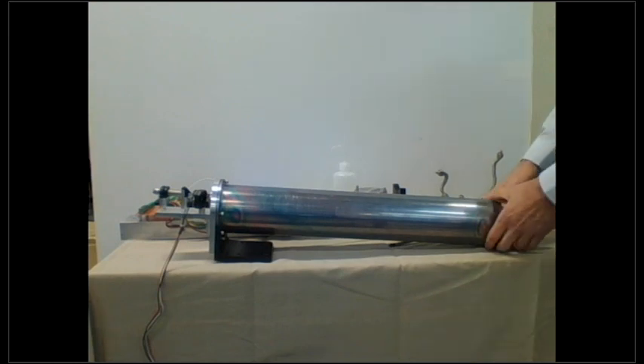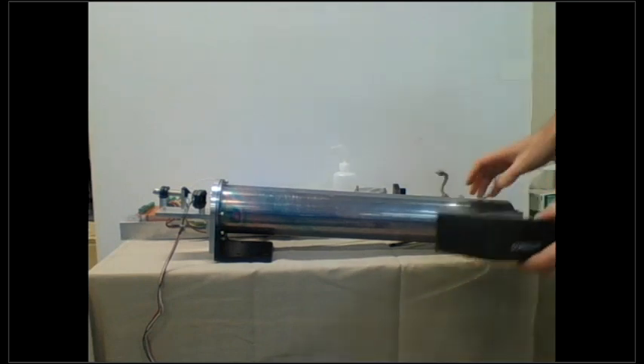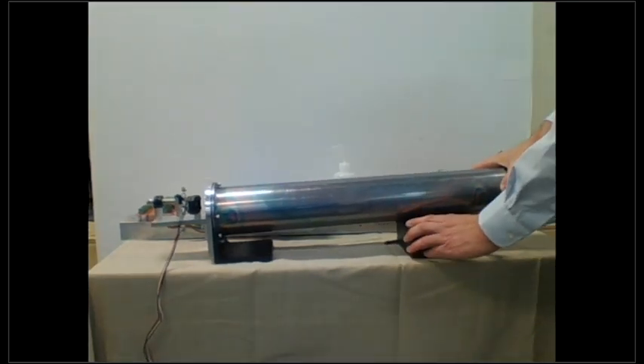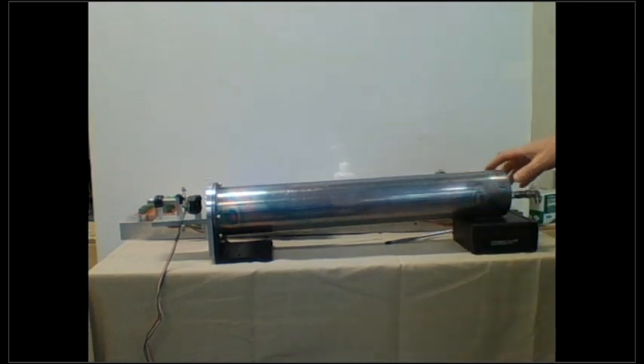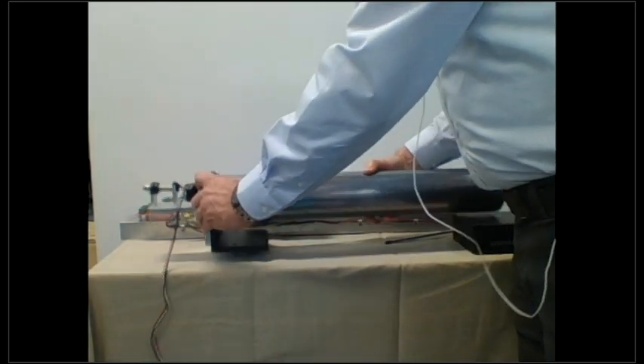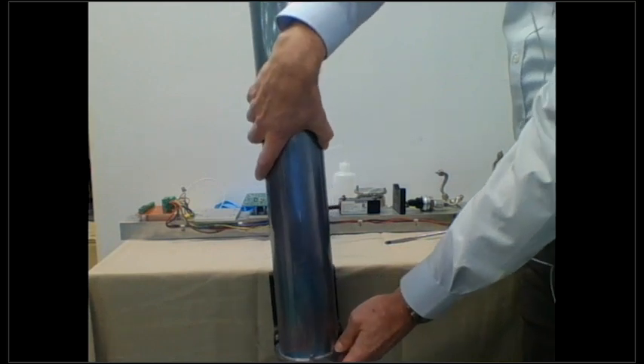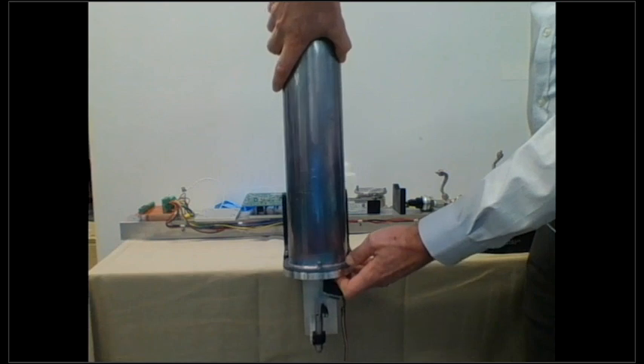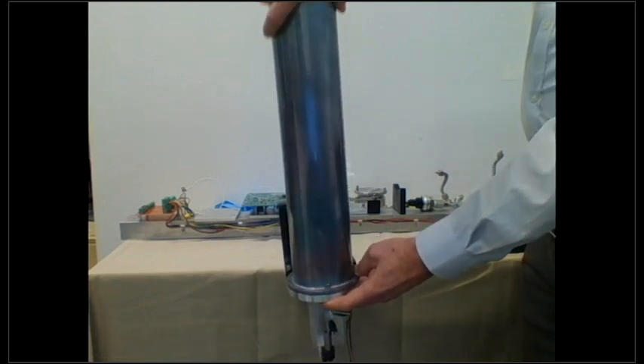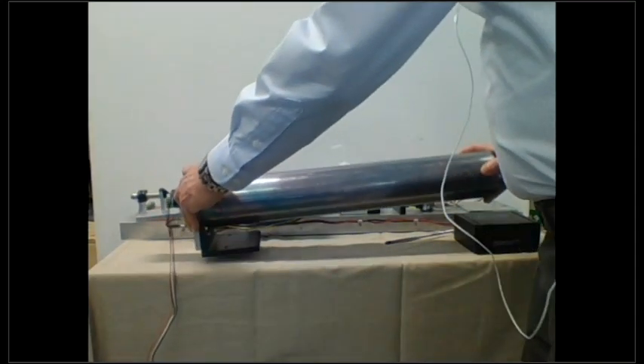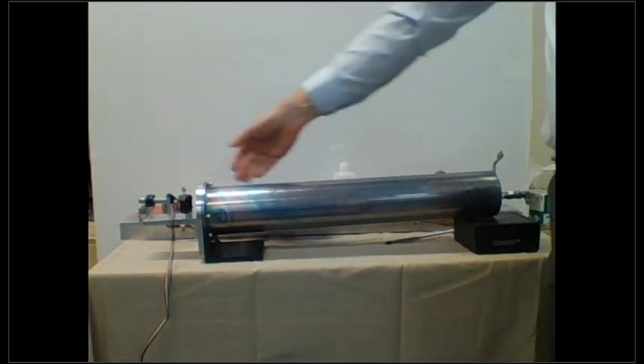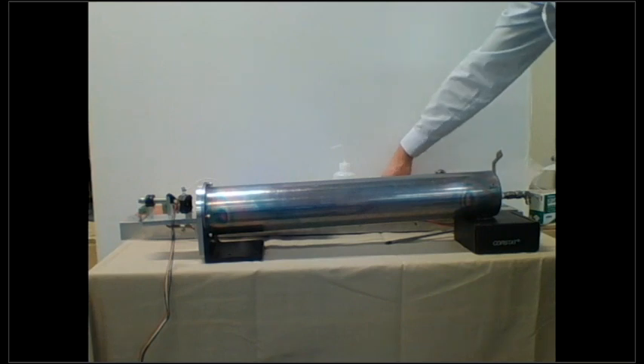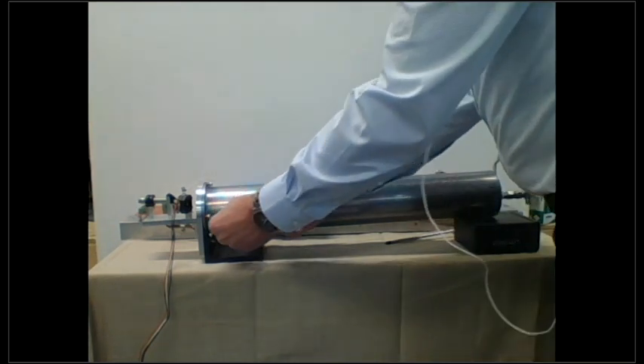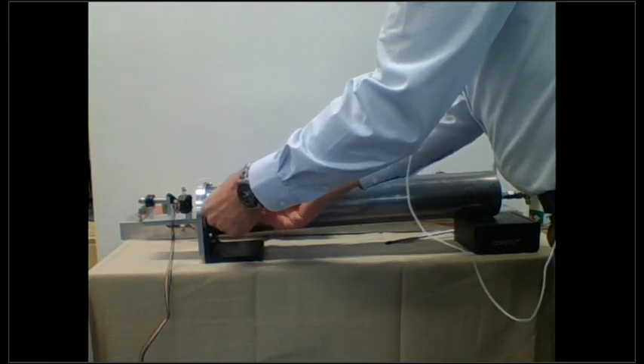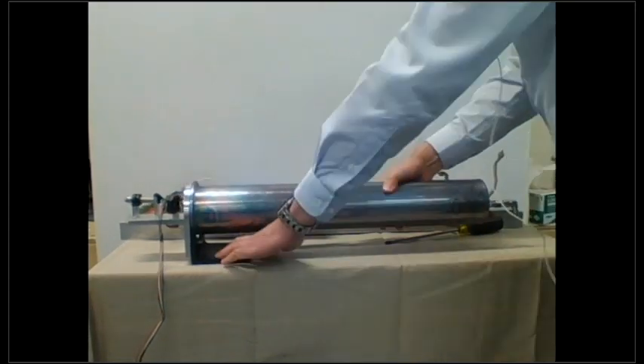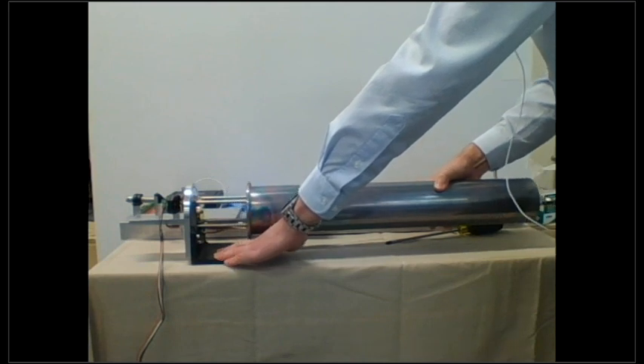So once you have the cell on the bench, you can operate on it. One thing I found that's really handy, if you have a vise or a 90-degree bracket, it's a little more convenient if you can actually put the cell vertically like this, because you're going to have access to these bolts here to take the cell shroud off. In this case, for the purposes of our demo, I'm just going to do it on the bench. I've already taken most of the bolts out. There's just a couple here. So using an Allen key type of wrench, I can simply undo the bolts. Set those aside. And once I do that, essentially the whole shroud assembly can be pulled off.